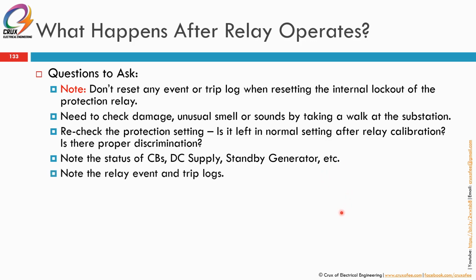So once you've gone through the bigger picture, you go straight to the relay and note the relay events and trip logs. What happened just before the tripping, and what is the trip log? What was the trip cause due to? Overcurrent, a fault, overload, or differential. So all these trip logs will tell you this, unless you are using the normal electromechanical relay or even a numerical relay, which does not have this kind of event or trip log. So it depends on what kind of protection relay you have.